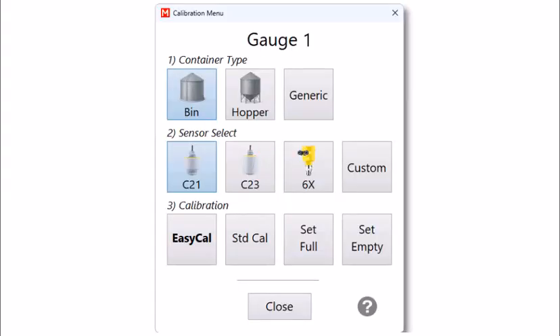There are two remaining calibration options for the standard bin: Set Full and Set Empty. Your initial calibration must be performed using either Easy or Standard Calibration. Set Full and Set Empty can be used later to make minor adjustments if there are small errors in the original calibration. You may notice that even though your sensor is reading full based on your original calibration, you may actually have additional space left to fill due to the coning tendencies of wet bin contents.